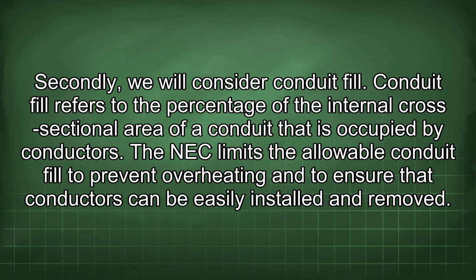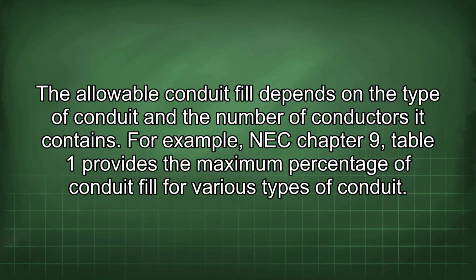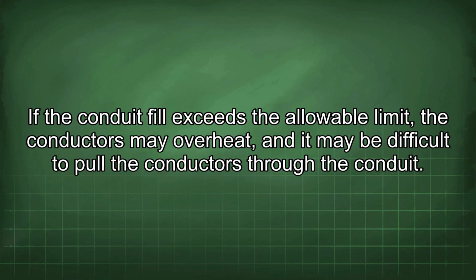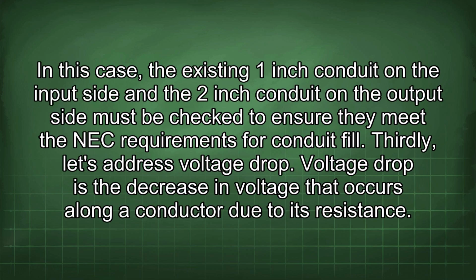Secondly, we will consider conduit fill. Conduit fill refers to the percentage of the internal cross-sectional area of a conduit that is occupied by conductors. The NEC limits the allowable conduit fill to prevent overheating and to ensure that conductors can be easily installed and removed. The allowable conduit fill depends on the type of conduit and the number of conductors it contains. For example, NEC Chapter 9, Table 1 provides the maximum percentage of conduit fill for various types of conduit. If the conduit fill exceeds the allowable limit, the conductors may overheat, and it may be difficult to pull the conductors through the conduit. In this case, the existing 1-inch conduit on the input side and the 2-inch conduit on the output side must be checked to ensure they meet the NEC requirements for conduit fill.